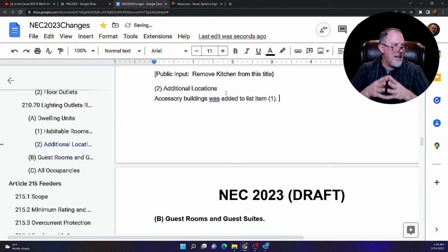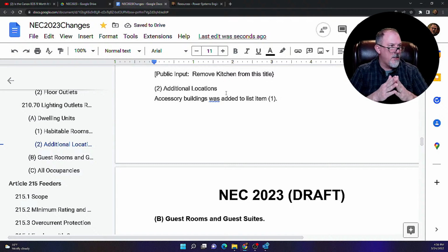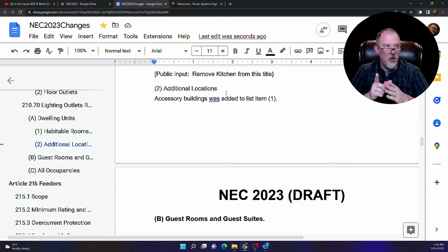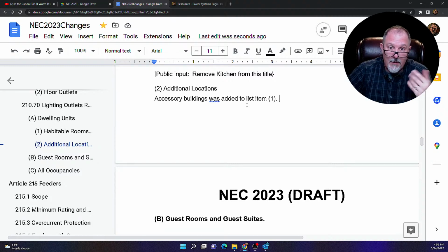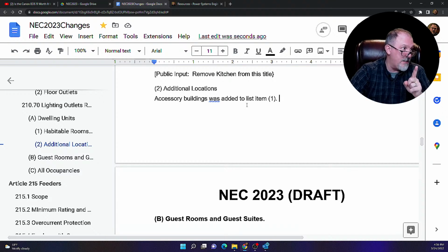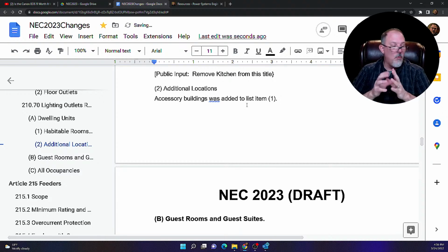At least one lighting outlet controlled by a listed wall-mounted control device shall be installed in hallways, stairways, attached garages, detached garages, and accessory buildings with electric power. So if you have an accessory building and there's electric power going out to there, you're going to need at least one lighting outlet. Makes sense, right? I don't see why it wouldn't. That's the first change we did there, in list item 1.